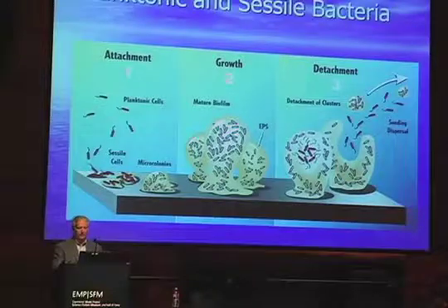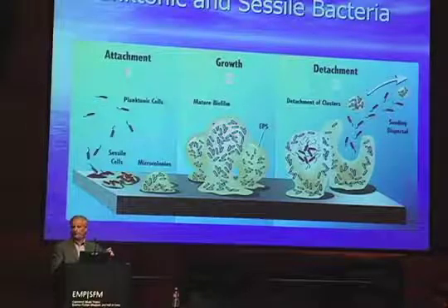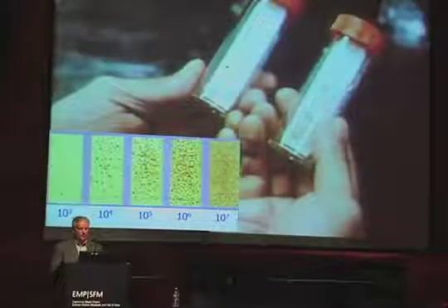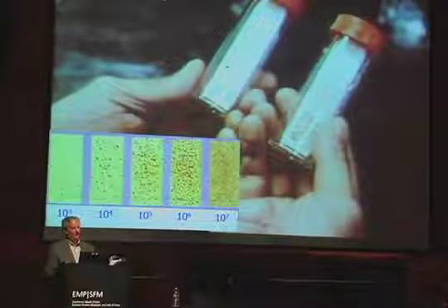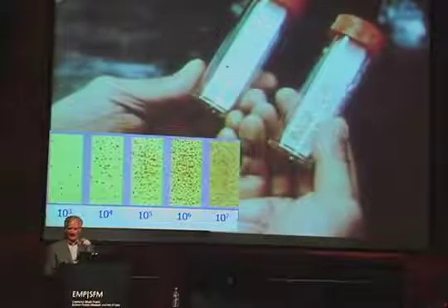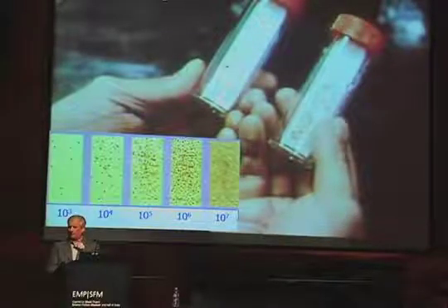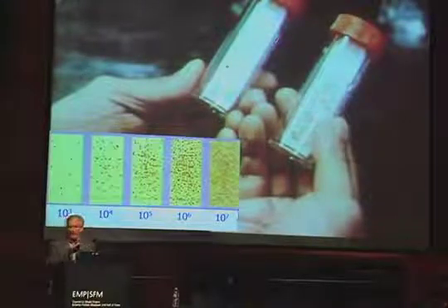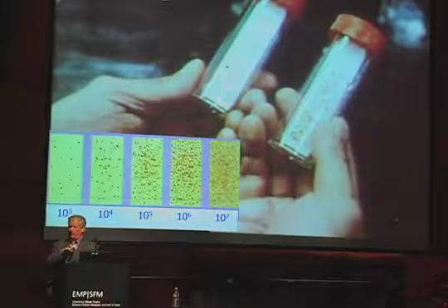So just so you're aware, just because you measure biological activity in bacteria strips doesn't mean you have a good and healthy system. One of the ways that everybody seems to, and probably the best way from a field perspective, to measure bacteria is through the dip slides. You've probably seen the Hawk dip slides or the Orion dip slides. And basically what they do is they have an agar nutrient solution on the paddle itself.